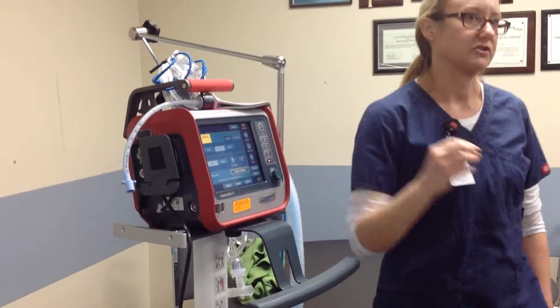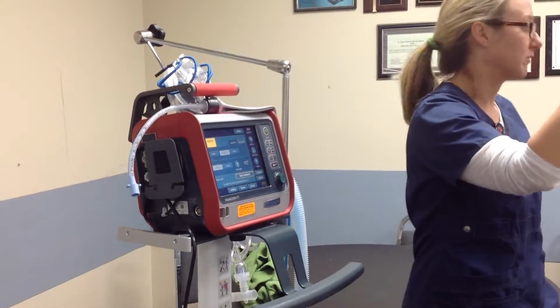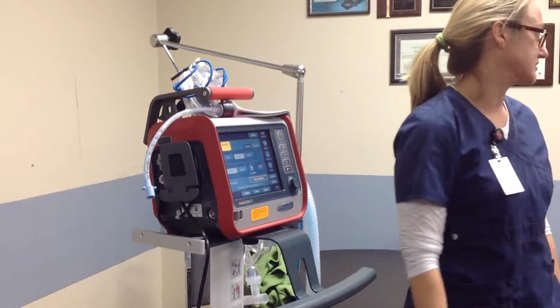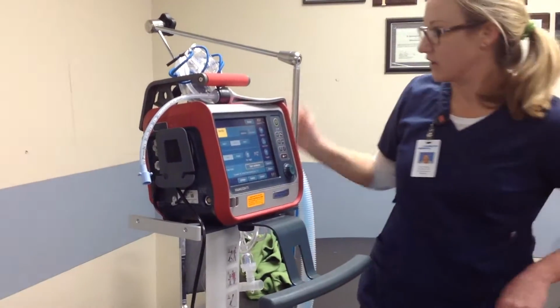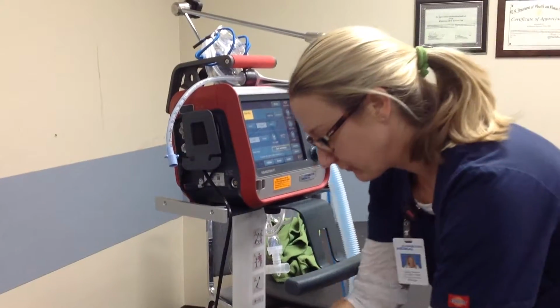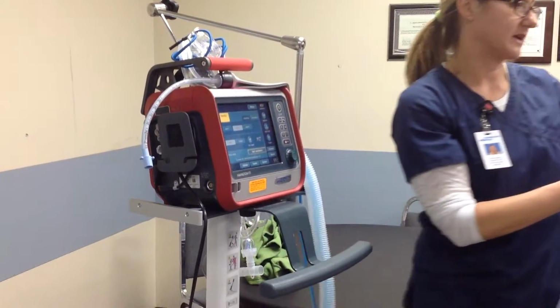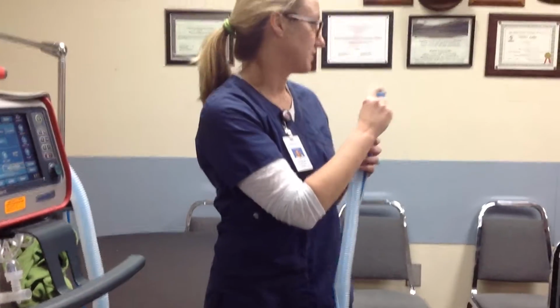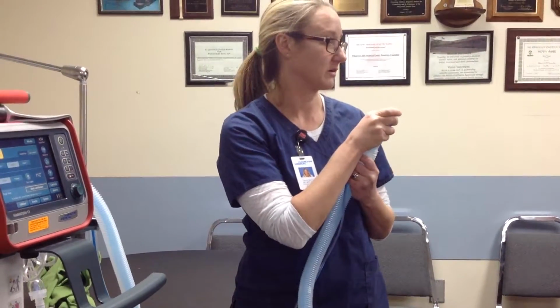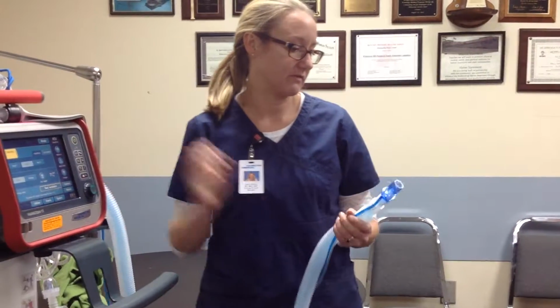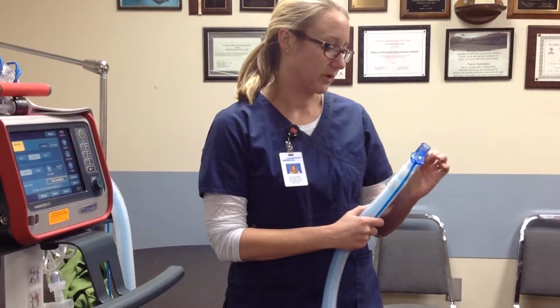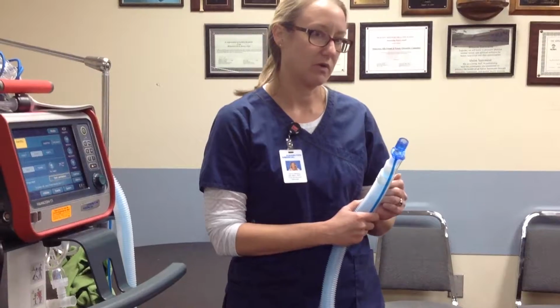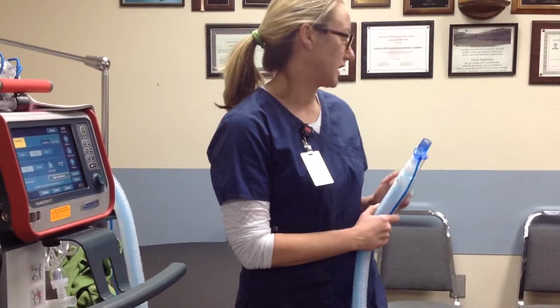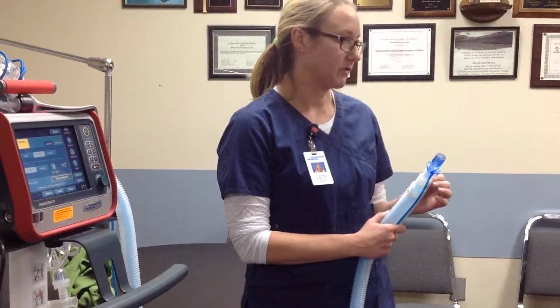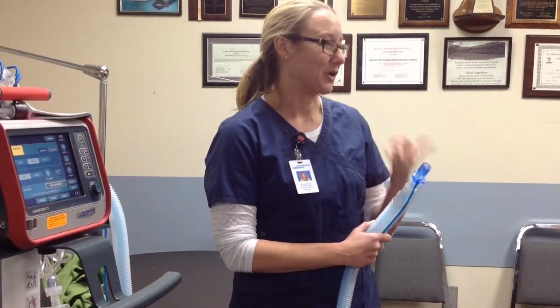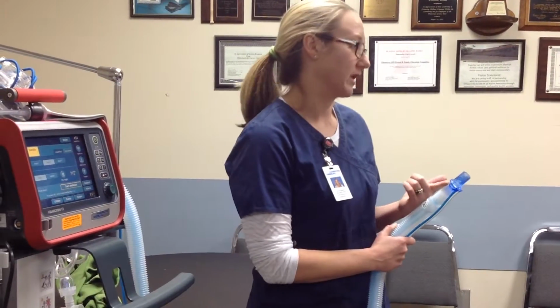It doesn't necessarily just, boom, go up to whatever pressure is required to put that volume into the patient's lungs. The other thing that you're going to notice here is that every ventilator has a flow sensor. This flow sensor just happens to be outside of the ventilator instead of inside of the ventilator. And so what it's doing from breath to breath is measuring inspiratory and expiratory flow rates, inspiratory and expiratory volumes, inspiratory and expiratory pressures. And from that information, it's calculating airway resistance and static compliance from breath to breath.